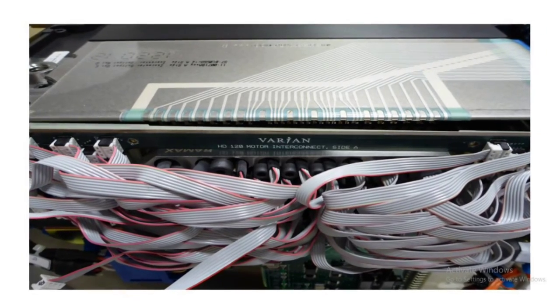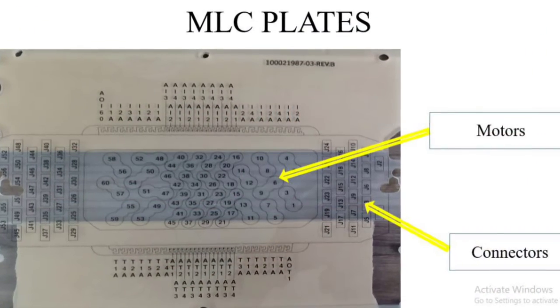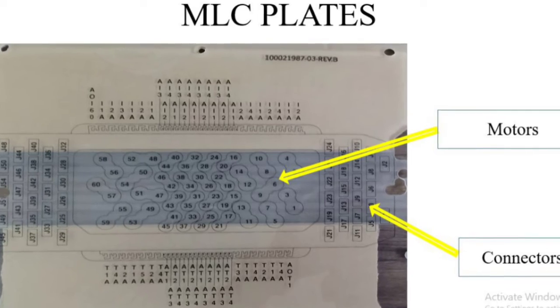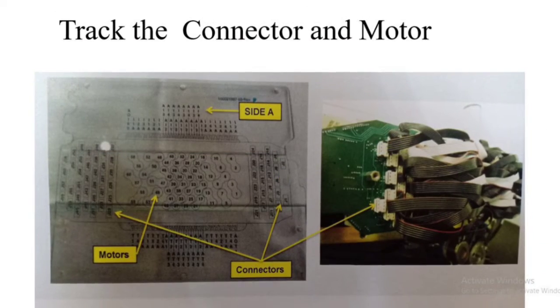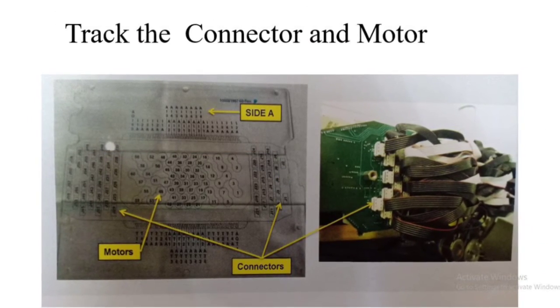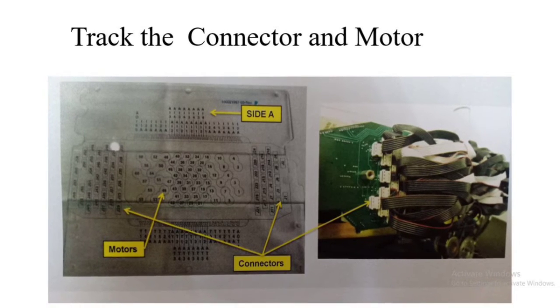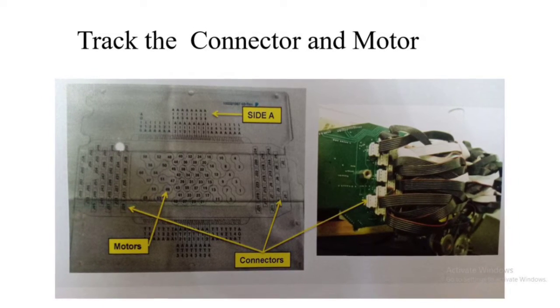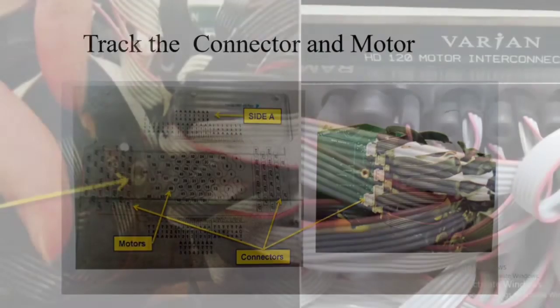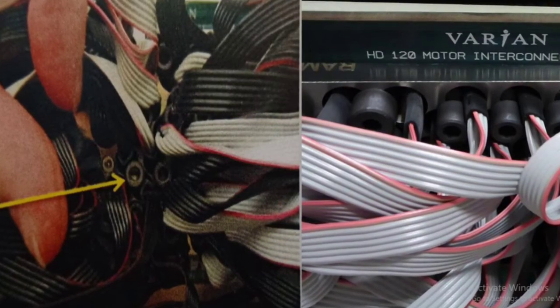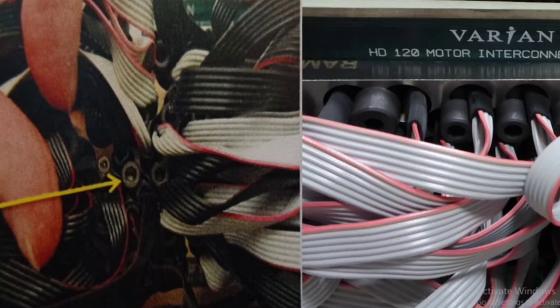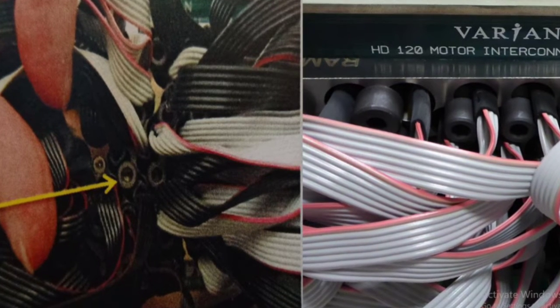This is the MLC plate which has the location of the motors and its connectors. Now we have to determine the location of the motors and its connector using these MLC plates. So first we will identify the location of the connector and we have to remove the connector. After removing the connector, we have to track the motor and unscrew the bolt as shown in the picture, and then we have to remove the old motor and replace it with the new motor.